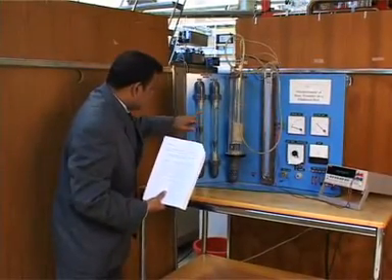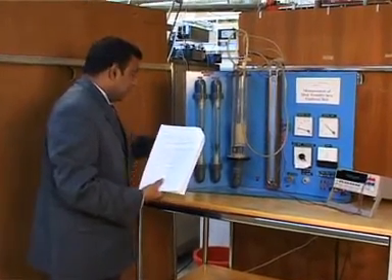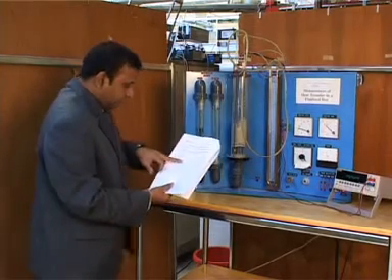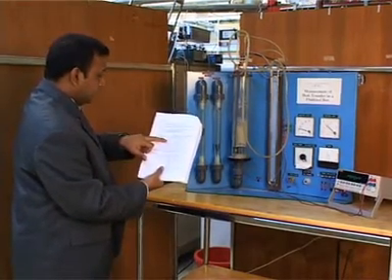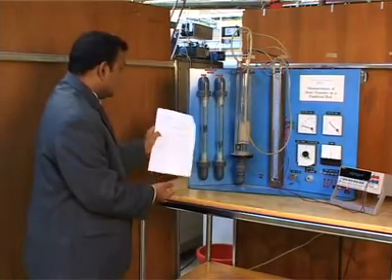To get that, you set the flow to a 12.5% reading on rotameter 1, because these two rotameters are scaled as percentages. They were calibrated before, so 0.5 cubic meter per hour corresponds to 12.5% on rotameter 1.